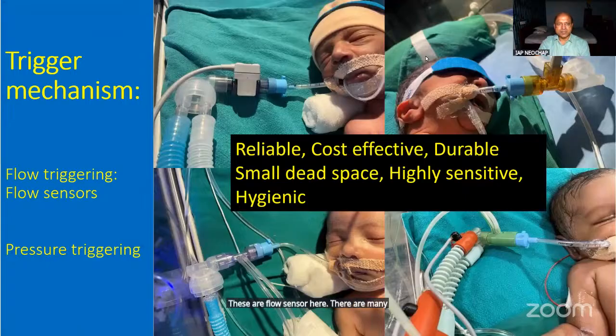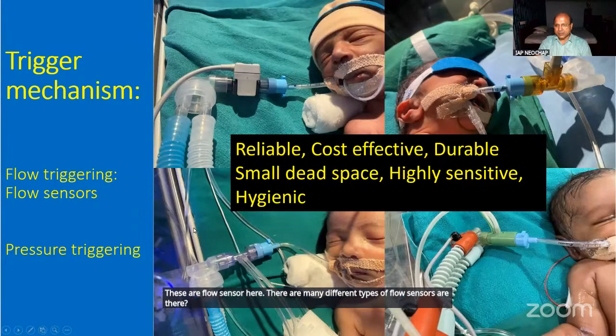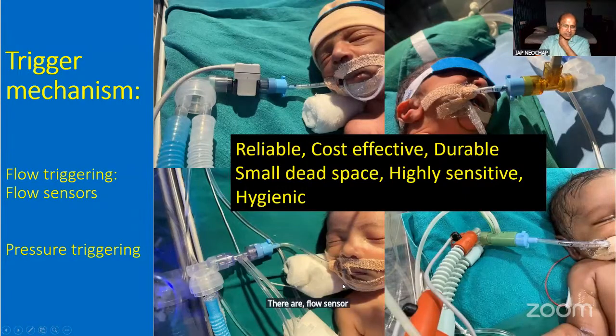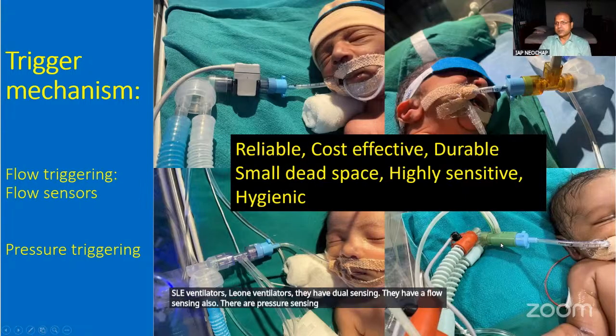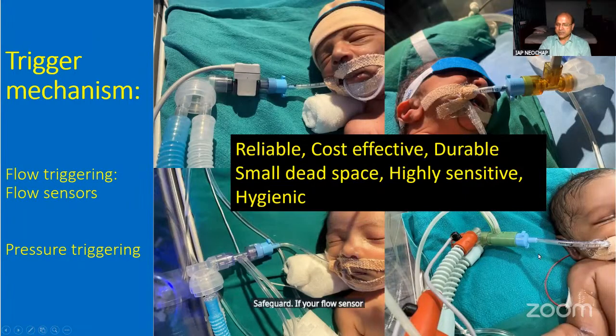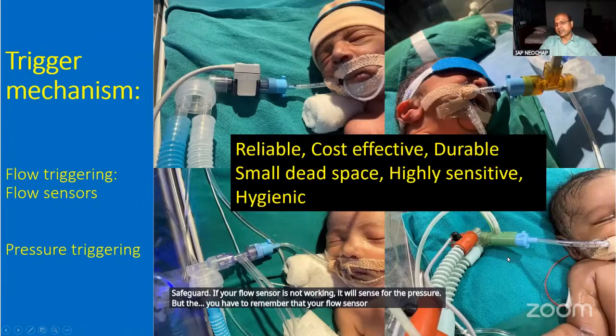Okay. There are many different types of flow sensors. Few of the ventilators give a proximal pressure sensor also. And the benefit of that is, if your flow sensor is not working, it can synchronize with the pressures. Like SLE ventilators, Leoni ventilators, they have dual sensing. They have flow sensing and also pressure sensing. So you have dual sensing, that is a safeguard. If your flow sensor is not working, it will sense the pressure. But you have to remember that your flow sensor should be working.